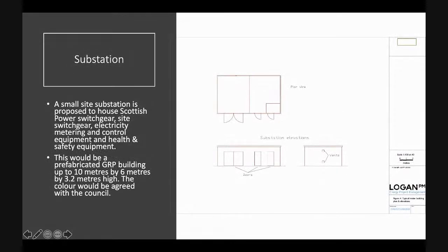There's also a small substation building included in the compound, which is a glass reinforced plastic building that supplies all the equipment you would need. It's got all the electrical equipment we need to take the power from the batteries to the grid, and from the grid back to the batteries again. That's a prefabbed GRP building, 10 meters by 6 meters by 3.2 meters high, with a colour to be agreed with the council.